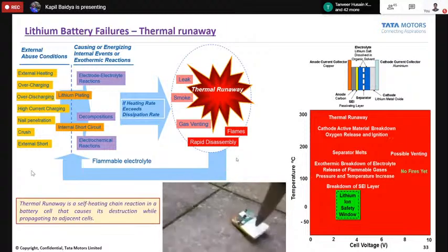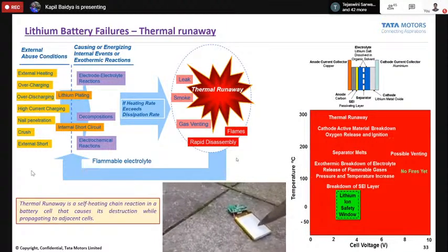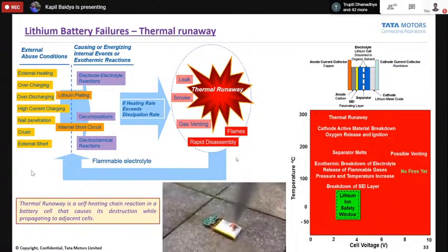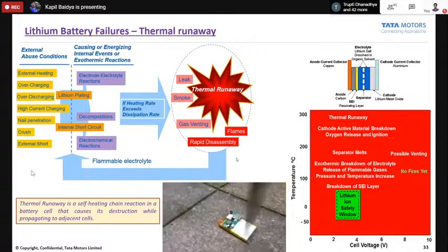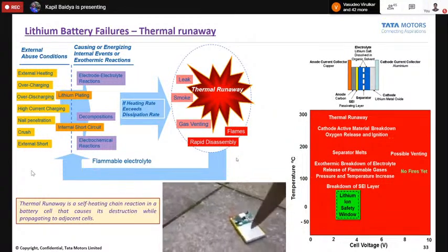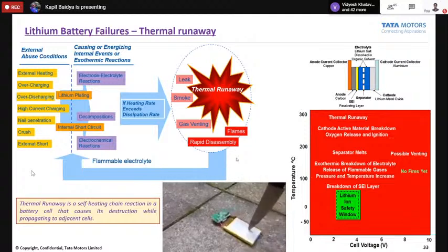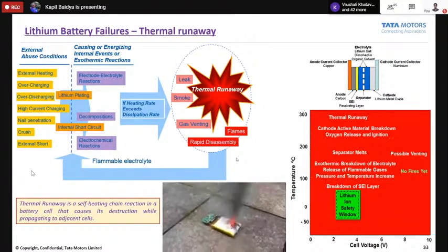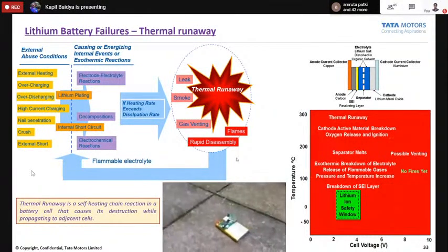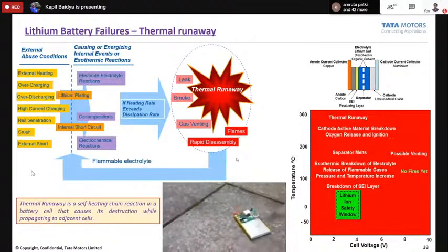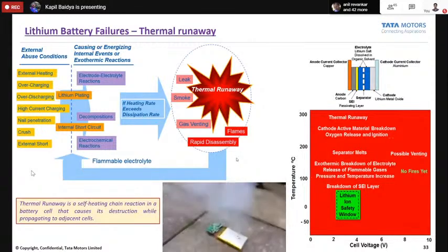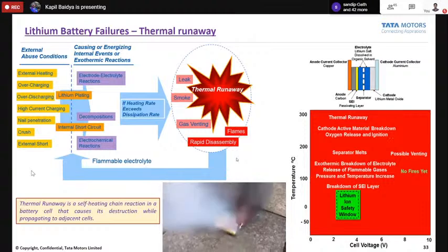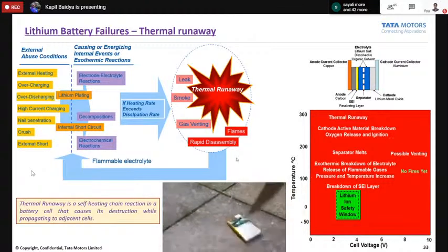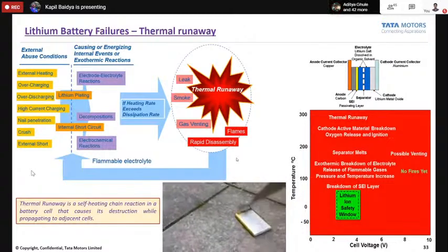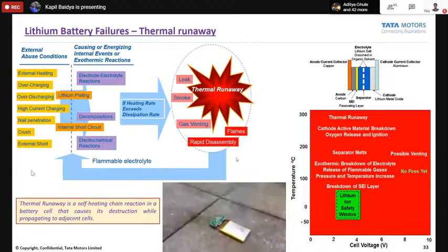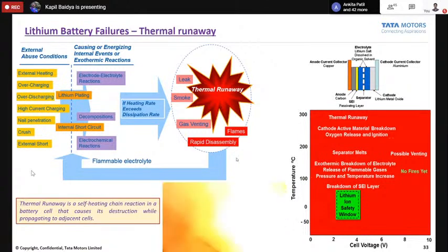When breakdown of the SEI layer happens at around 40 degrees centigrade, and around 100 degrees centigrade, the pressure and temperature increases, releasing flammable gases with exothermic breakdown of the electrolyte. But at around 100 degrees centigrade, no flame fires are seen yet. At around 180 degrees centigrade, the separator, which is polyethylene or polypropylene, will melt, and possible venting will happen. At roughly 250 to 280 degrees centigrade, cathode active material breakdown happens, oxygen releases, ignition happens, and eventually we see the thermal runaway.